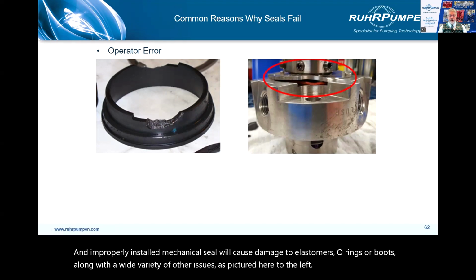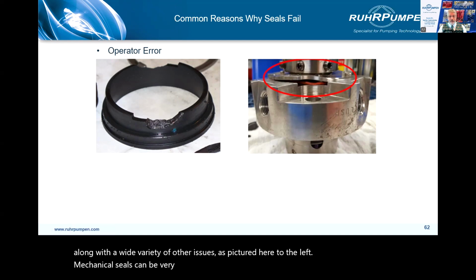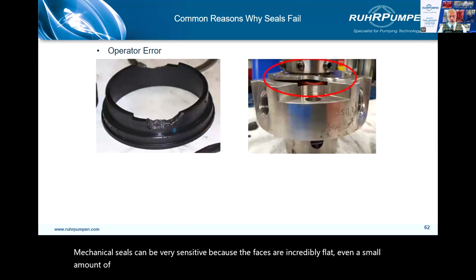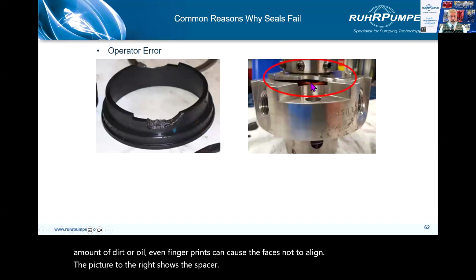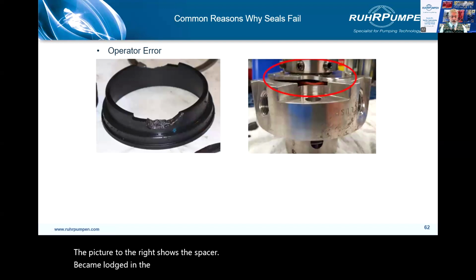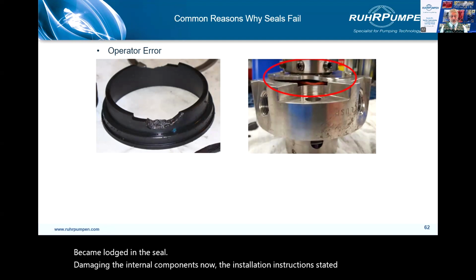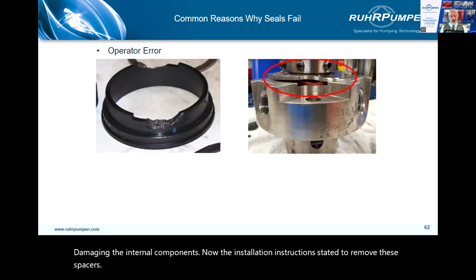Mechanical seals can be very sensitive because the faces are incredibly flat. Even a small amount of dirt or oil, even fingerprints, can cause the faces not to align. The picture to the right shows the spacer became lodged in the seal, damaging the internal components. Now, the installation instructions stated to remove these spacers before starting the unit.